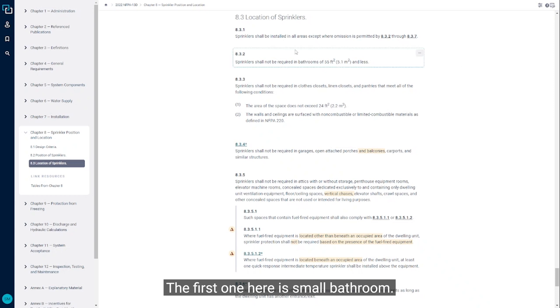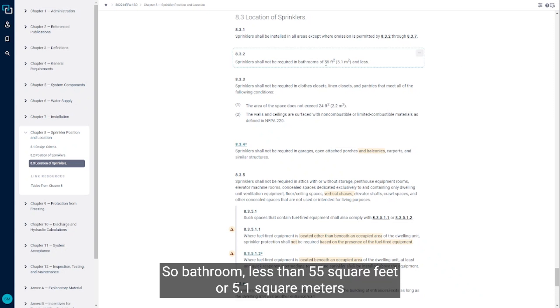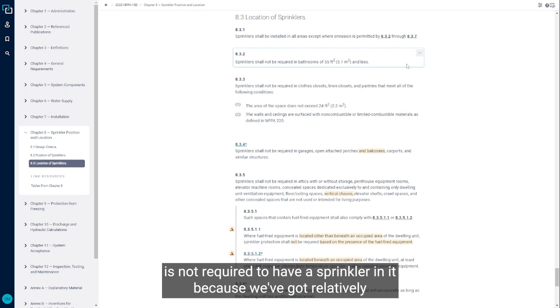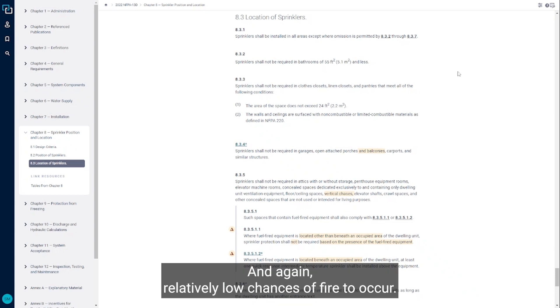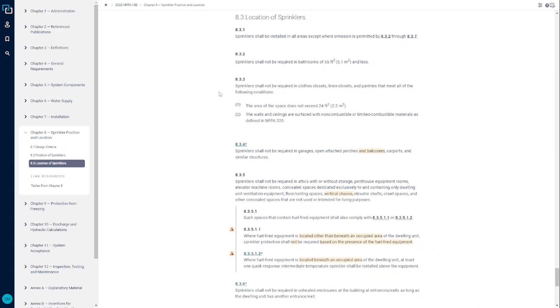The first one here is small bathrooms. A bathroom less than 55 square feet or 5.1 square meters is not required to have a sprinkler in it because we've got relatively low combustible loading in those spaces, and relatively low chances of a fire to occur.